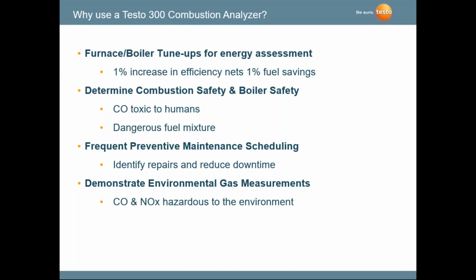Why are we using combustion analyzers today? Well, there are a few reasons that show you why we use combustion analyzers: boiler tune-ups, and certainly combustion safety, maintenance, environmental gas measurements. Really, what we're doing with a combustion analyzer is combustion safety, minimizing the carbon monoxide in the flue gases, minimizing the CO in the breathing air that we breathe, trying to get down to 0 parts per million in the ambient air.